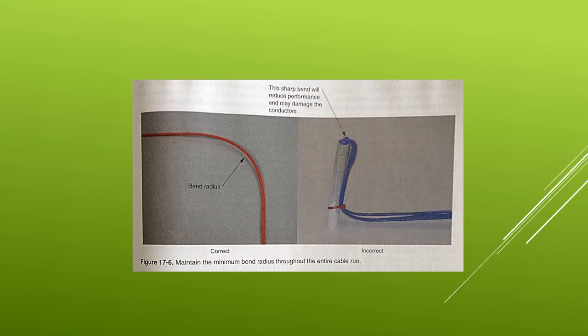The pulling tension of UTP cable is 25 pounds, and the pulling tension of coaxial cable is 35 pounds. Exceeding the pulling tension of either cable can cause physical damage and reduce the quality of the electrical signal. A cable bend should not be less than the established minimum bend radius. Doing so will degrade the quality of the electrical signal. The minimum bend radius is usually 4 times the overall diameter of the cable, but be sure to follow the manufacturer's recommendations. See figure 17-6.